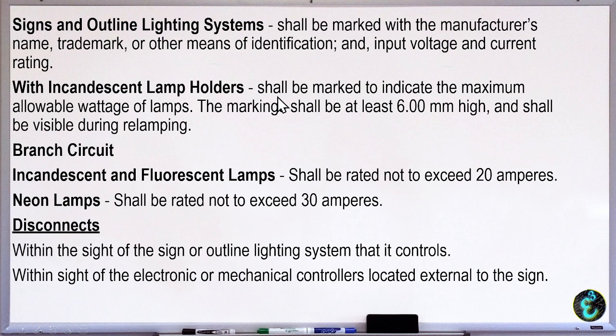With incandescent lampholders, kapag may mga lampholders sa loob, shall be marked to indicate the maximum allowable wattage of lamps. The marking shall be at least 6.0 mm high, ito ang minimum, and shall be visible during relamping. So in case na may busted at kailangan mong mag-troubleshoot, dapat klaro ang mga markings. For the branch circuit naman, incandescent and fluorescent lamps, this pertains to our signages, shall be rated not to exceed 20 amperes. Kapag neon lamp naman ang ginagamit, shall be rated not to exceed 30 amperes. So, ang maximum for incandescent and fluorescent, 20 amperes. Ang maximum for neon lamp is 30 amperes, kapag ginamit natin sila as lighting for signages.